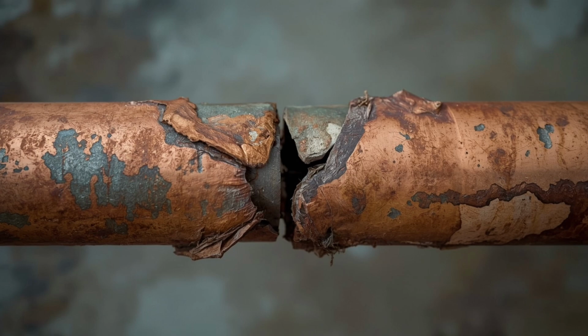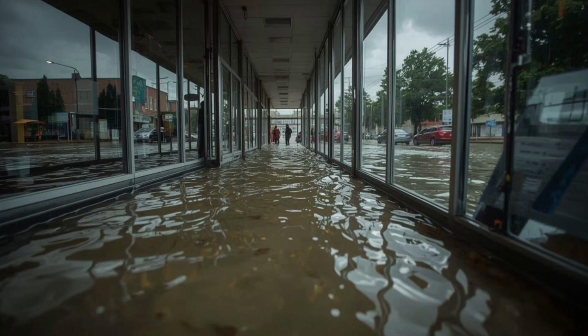The relief valves, typically spring-loaded poppet valves with discharge capacities of 50 to 100 gallons per minute, opened immediately when pressure exceeded their set points, but the discharge capacity was entirely insufficient to relieve the pressure being generated by the 17 pumping stations operating at maximum speed, and the sustained discharge at pressures far exceeding the valve design pressure caused erosion of the valve seat and disc, rapidly degrading the sealing surfaces and converting the valves from controlled relief devices into uncontrolled leak points that discharged water continuously without providing any meaningful pressure reduction in the system.